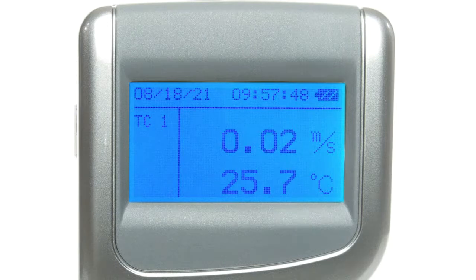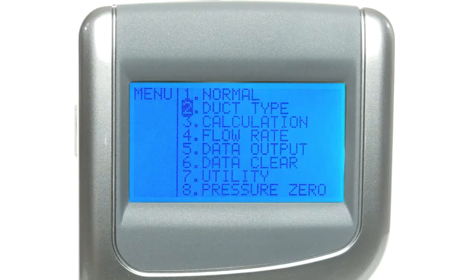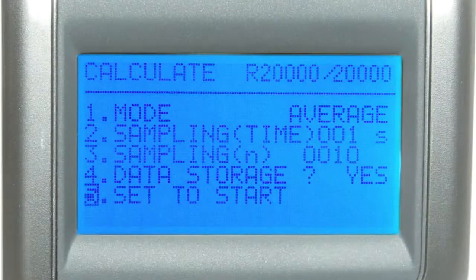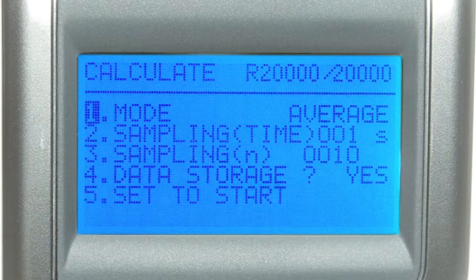In calculation mode, the maximum, minimum, and mean of measured data is automatically calculated for you. To use this mode, navigate to its setup section via the main menu. On the following screen, you'll find all the adjustable parameters for this mode, but also an indication of the available memory for future measurements. The first parameter you can adjust is the mode.